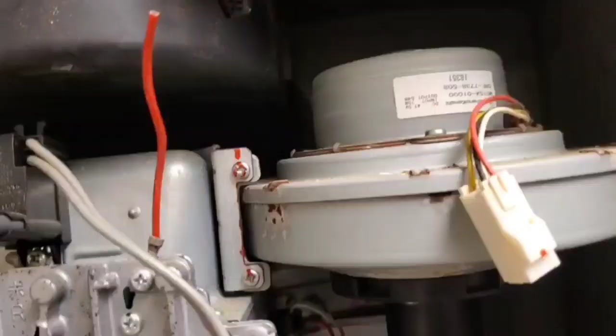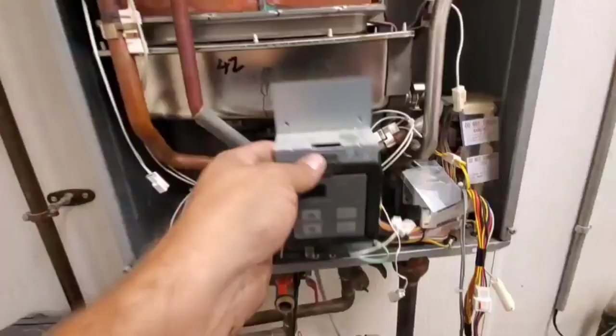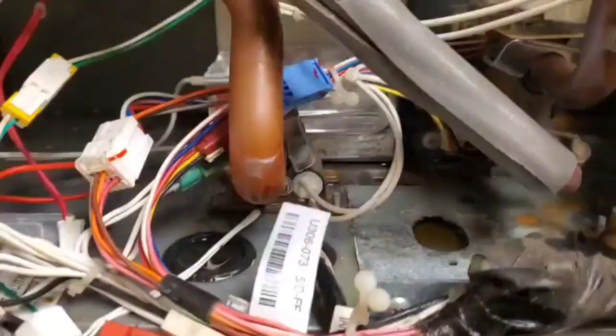Then you take out those two screws, and that's the only thing holding in the combustion blower. Pull the controls down out of the way, and now the only thing connecting the heat exchanger is the pipes, so now you go about unhooking the pipes.